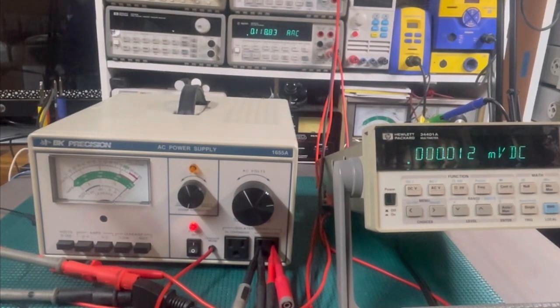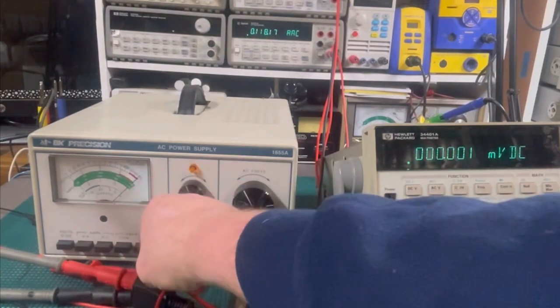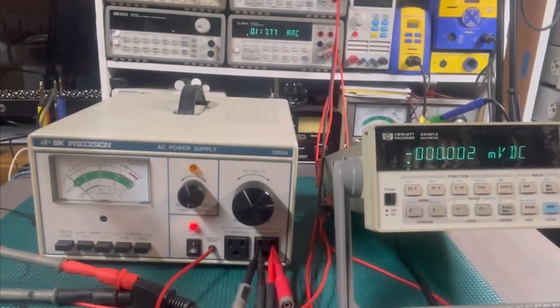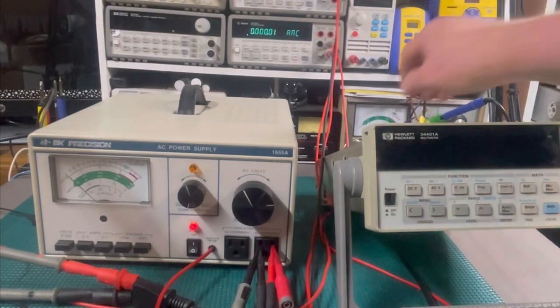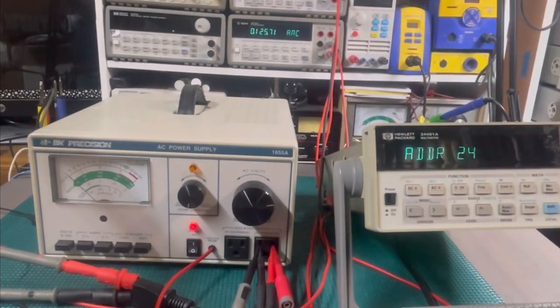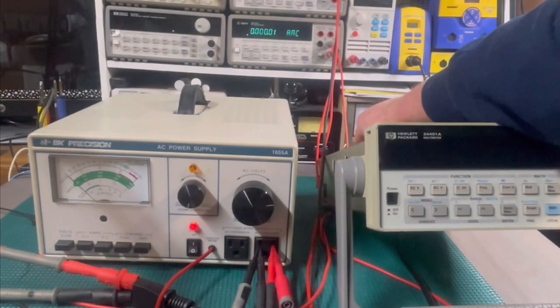So that's going to be a problem using the leakage detector, the leakage probe, and I'm not sure about the amps, because let me show you what the amps are doing. Okay, now that looks like 0 from your point of view. Let's see if you can see it move. I see it move. I don't know if you guys do, but I see it move. And as you can see on the meter, we're only drawing a little over 1/10 of an amp. So that really corresponds to about what that gauge might be moving, because 1 amp would be way up here.